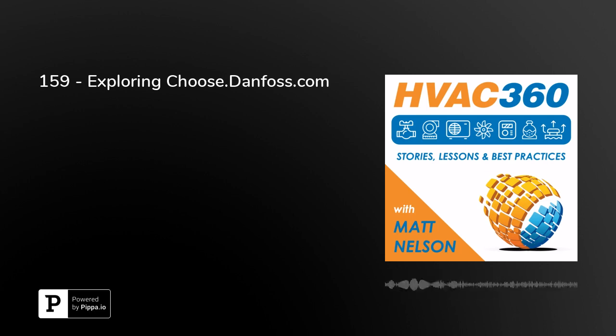And the TXV superheat tuner is just meant to help you speed up the adjustment process, because it'll look at the current superheat, your target superheat, and try and give you an approximate number of turns you should adjust your TXV. So it's pretty useful that way.